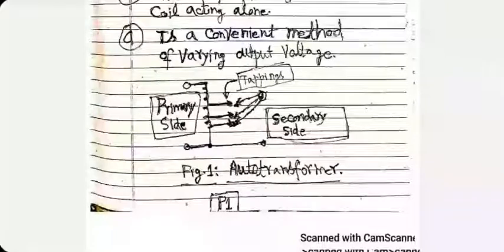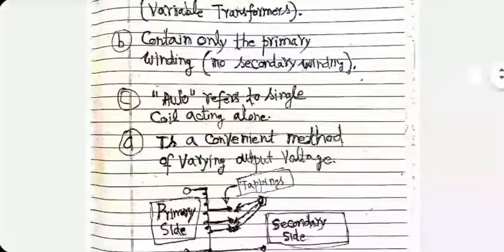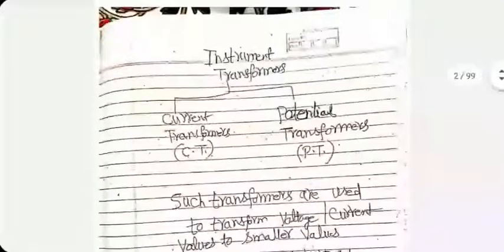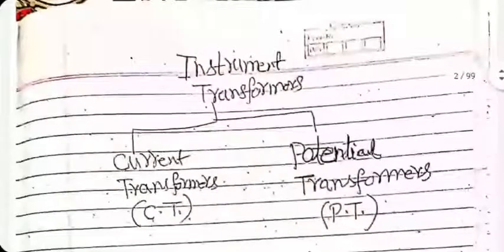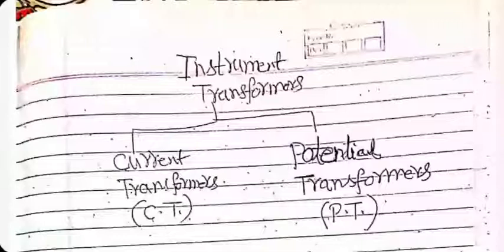And then there are other kinds of transformers also. They are called instrument transformers, which are used primarily for measurement instruments. They can be both current and potential transformers. The problem is, if you want to measure a very high current, instruments will simply burn out, no matter how well you have designed the instruments. There's no way you can measure 100 ampere current using a conventional instrument. Even the best ammeter would burn up.